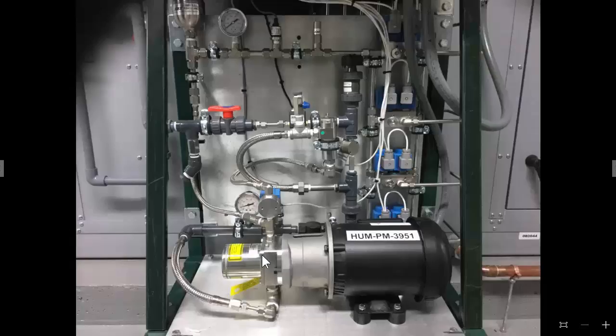So as this pump is running, you can feel this discharge line here, or much of this line, and you can feel the pulsing. Well, as soon as you feel the line going past this pulsation dampener, it is not vibrating as much. So this pulsation dampener is absorbing that vibration, and it helps throughout the system to keep vibration down. Now, Danfoss pumps have 5 pistons in them, and Danfoss says it's not necessary to have a pulsation dampener, but I have been putting them on because there still is some vibration that comes through these systems, and once you do put a pulsation dampener on, the vibration does diminish quite a bit. Now, vibration, pulsation, is system dependent.